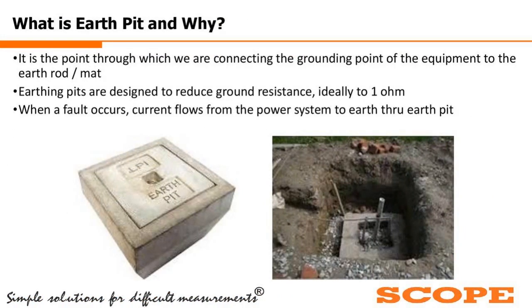What is an earth pit and why is it required? It is the point through which we connect the grounding point of the equipment to the earth rod or an earth mat. Every equipment is provided with a functional earth or instrument earth, so we need to connect that instrument to a point. We know this as the earthing point, but what is inside is actually the earth pit. Earth pits are designed to reduce ground resistance, ideally to a zone of 1 ohm or so. When a fault occurs, the current flows from the power system or the equipment to the earth through the earth pit.